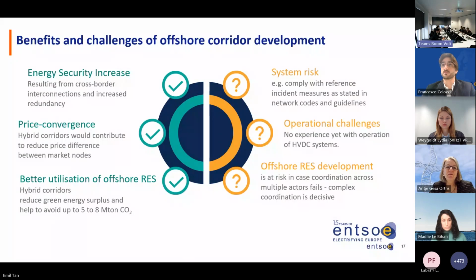So the headache we have when wanting to build this is the system risk. If we are not able to isolate faults and minimize the impact of losing something - which always happens in the system, though you don't notice because it's so fast, and protection systems help save the system - if we lose too much energy, we would put the system at risk. As you might remember, 3,000 megawatts for the continental system, or 1,400 megawatts for the Nordic system, and here we discuss 2 gigawatt lines, so 2,000 megawatts. So if one line to the system goes off or anything happens, we would have a problem.